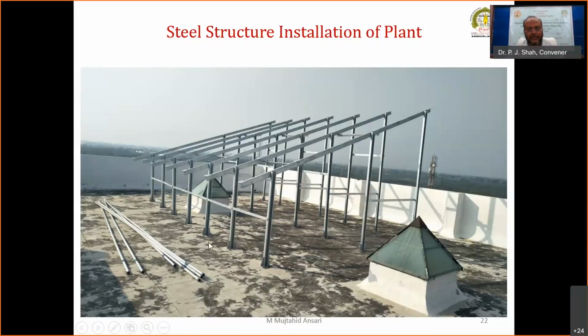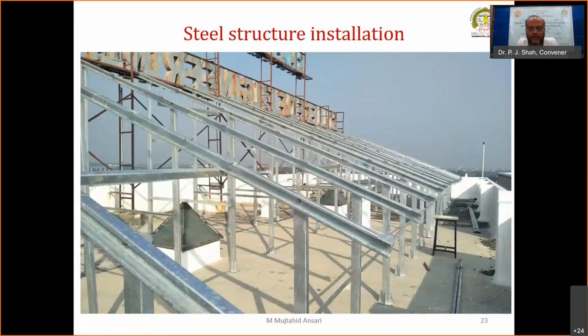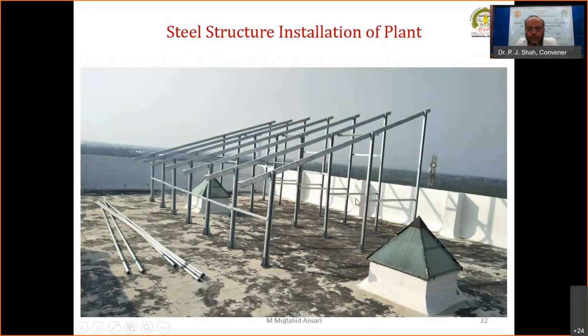One more thing is that it is standard practice to use a pedestal of the size 400 mm by 400 mm by 400 mm, a cube over the steel structure, to avoid the wind pressure. But to reduce the weight over the rooftop, we have designed a new civil pedestal. We can see here the distance between these two beams is equal to the distance between alternate legs. So we install the plant in such a way that at least one leg is over the beam, which avoids the point load over the slab.